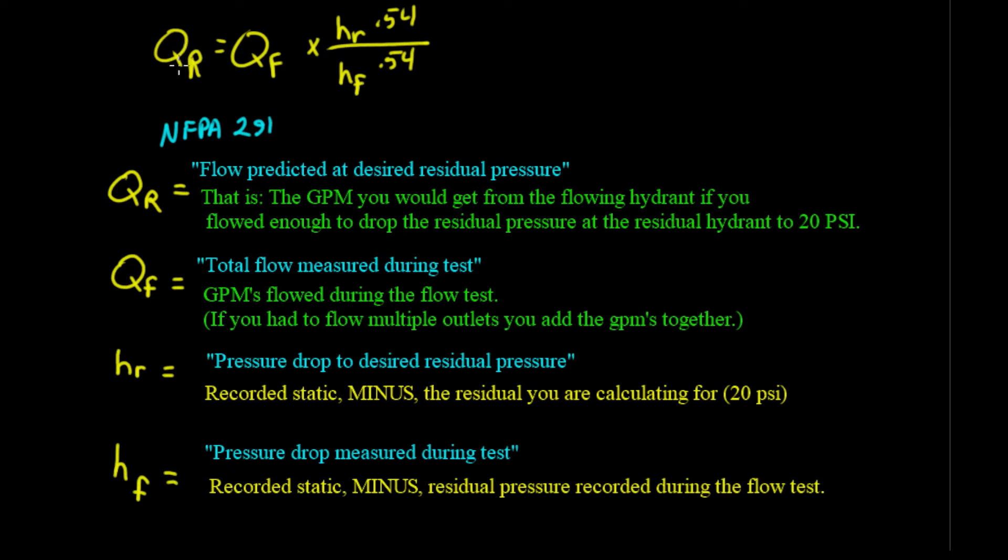What do the variables mean? QR, that's the gallons that we want if we drop it down to 20 on the residual hydrant. Now the QF is the actual gallons we flowed on the hydrant test just a minute ago. In this case, it's going to be 839.53 gallons. HR in this equation, that is kind of confusing. It's actually a word problem. It says pressure drop to desired residual pressure. But what you have to do is you take your recorded static minus the residual you're calculating for, which would be 20 PSI in this case. Do that. That's where you get HR.